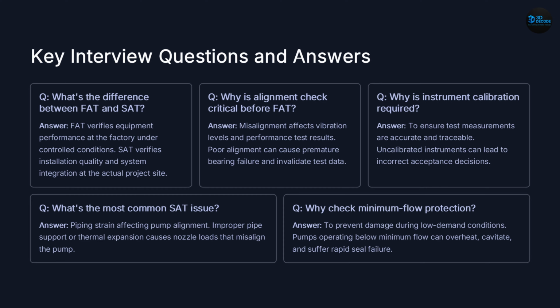Why is instrument calibration required? Because inaccurate instruments create inaccurate acceptance decisions. What's the most common SAT issue? Piping strain. Because piping loads often distort alignment after installation. Why verify minimum flow protection? Because low flow operation can quickly damage pumps through overheating and recirculation. These questions appear frequently because they reveal whether an engineer understands commissioning fundamentals or only equipment theory.